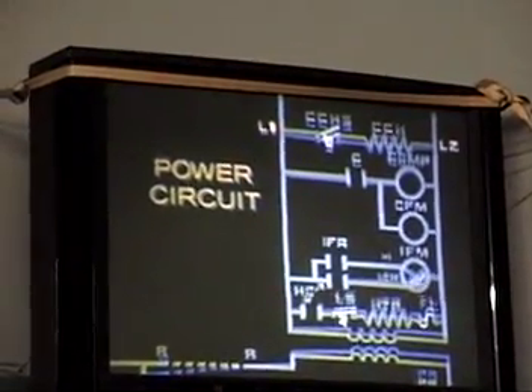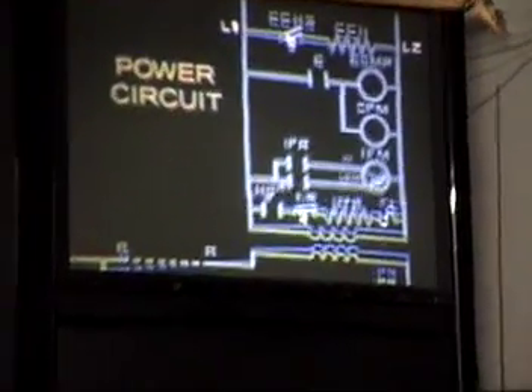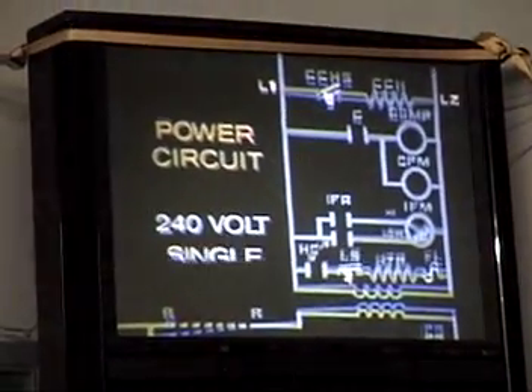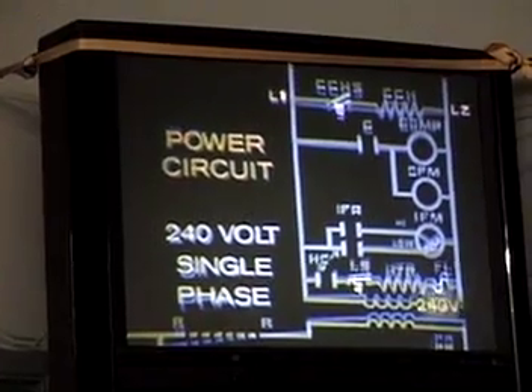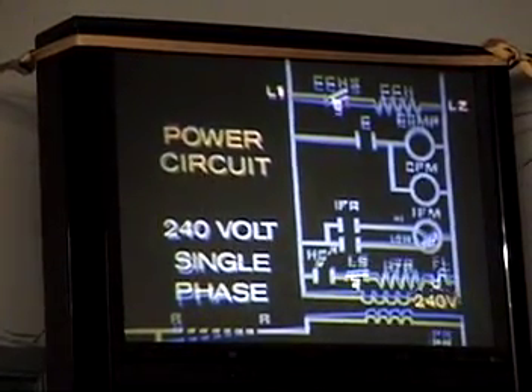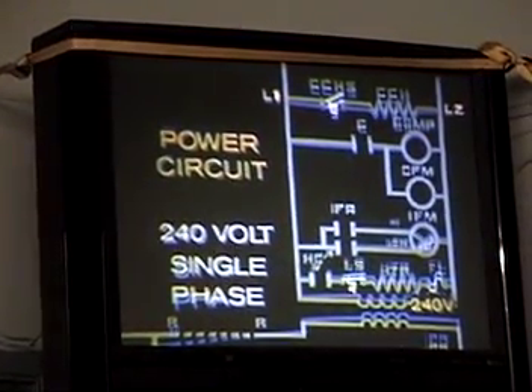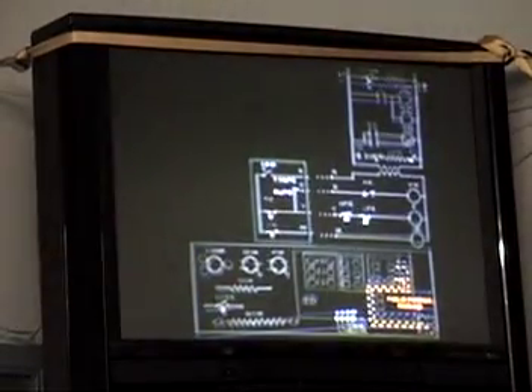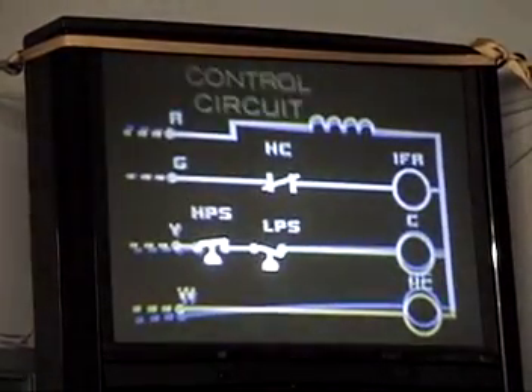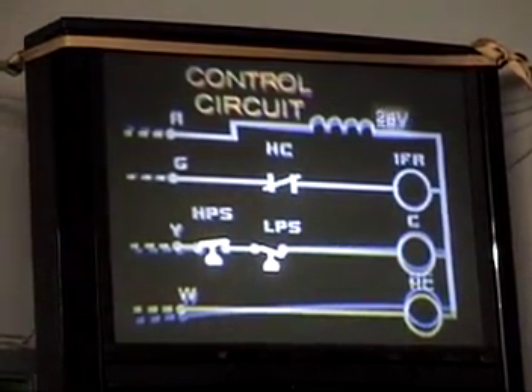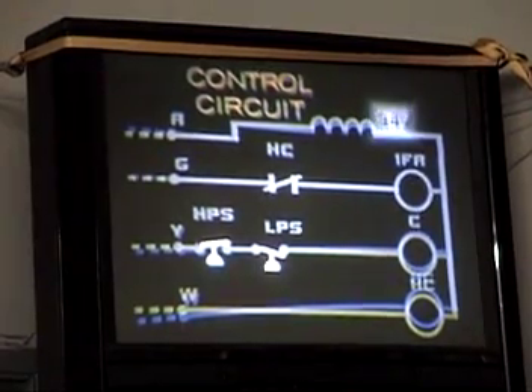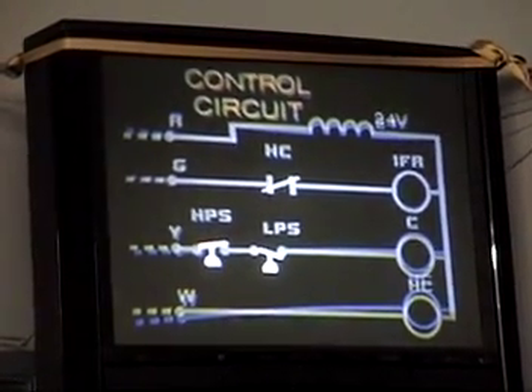The power circuit operates at line voltage. In our case, it's 240 volts single-phase power. In other cases, it could be some other voltage and either single or 3-phase. The control circuit, which in our case operates at 24 volts. Other control circuits operate at 115 volts or even 240 volts.